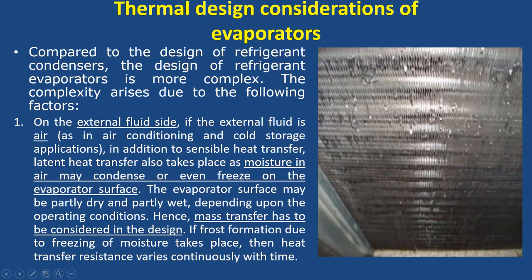The evaporator surface may be partly dry and partly wet depending upon the operating conditions. Hence, mass transfer has to be considered in the design. If frost accumulation is there, then the heat transfer resistance varies continuously with time, because frost accumulation reduces the rate of heat transfer. So this consideration should be there while designing, because here we cannot calculate the total heat transfer by using the formula Cp delta T.